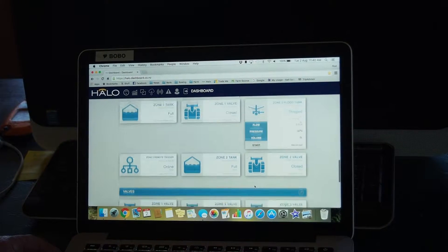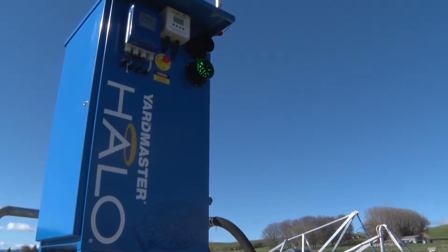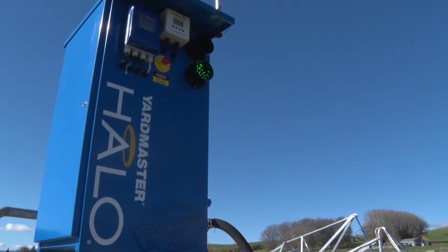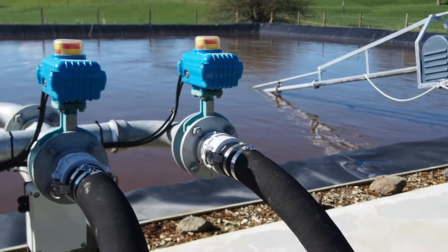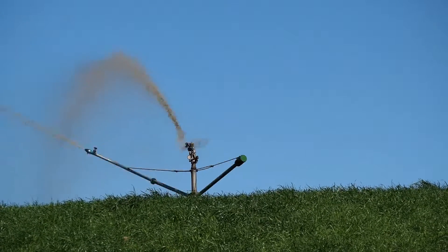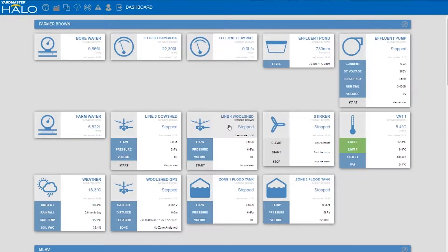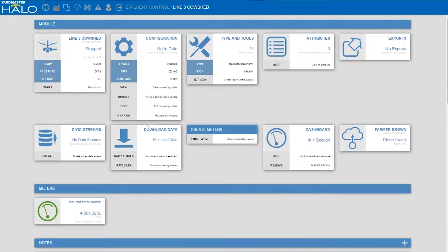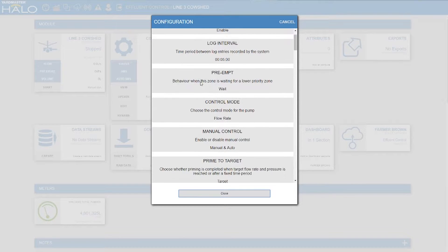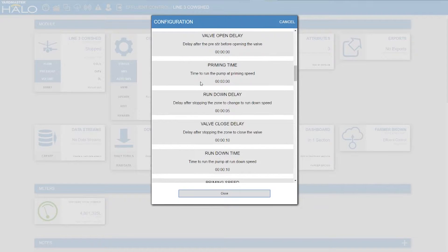Within each zone you can set up a schedule during the commissioning phase. When you push the button to start that irrigator, the pump and stir will start, the valve will open and it will go through that sequence to run the irrigator. That same sequence in reverse will be implemented when you stop the irrigator. We go into the irrigation zone — in this case it's the cow shed side — click onto that module, and within the module we have options to view the configuration with multiple adjustable points for pump control.